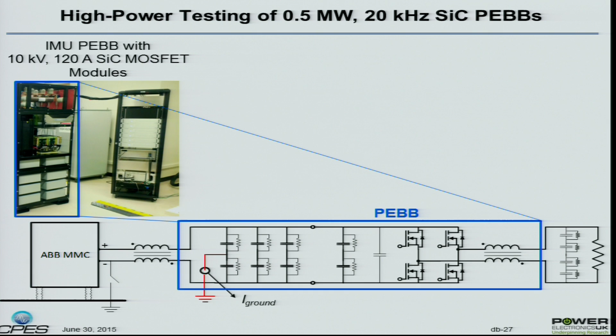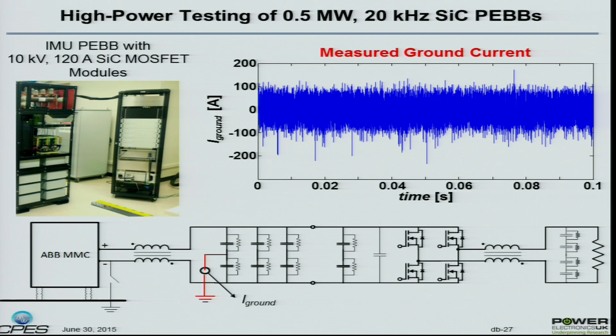The one I've just shown, PEB, we're testing now in Florida, collaborating with another university. These are the common mode currents measured on the system. We had huge problems — our control system was tripping all the time. The system is designed to inject currents of about 100 amperes, but the common mode currents exceed 200.